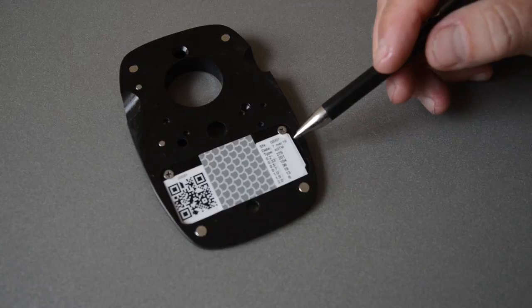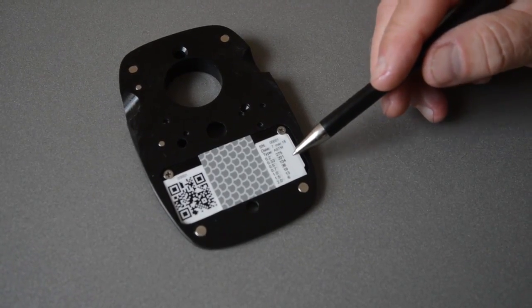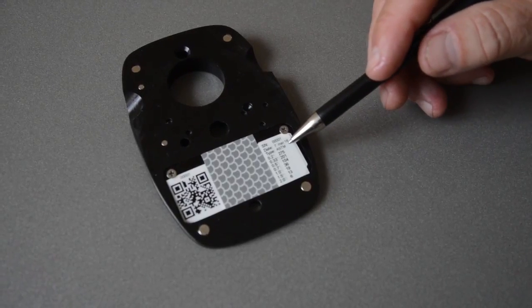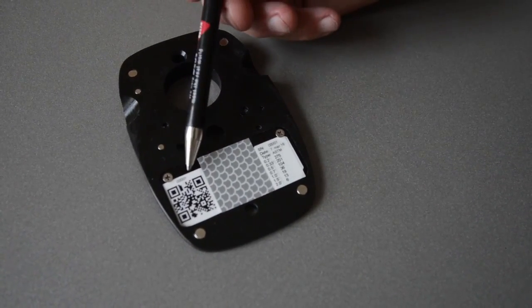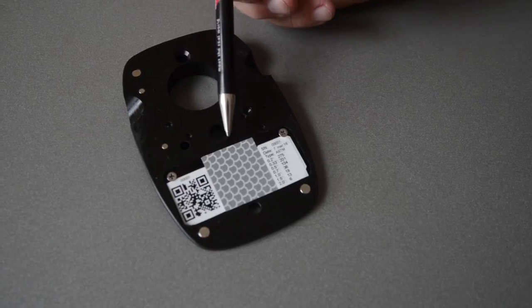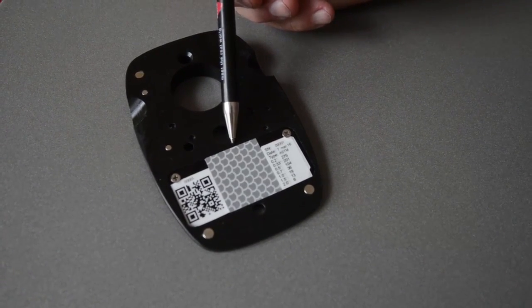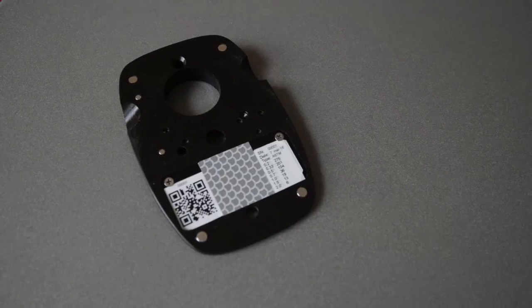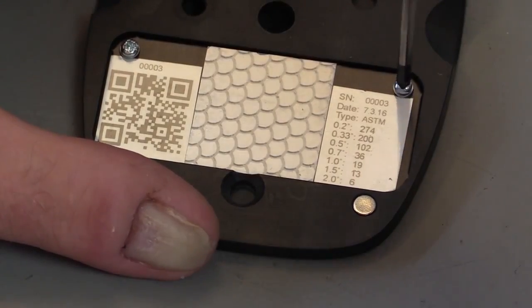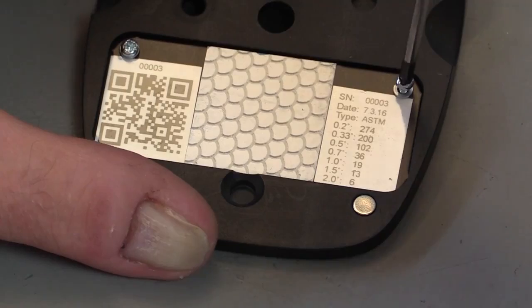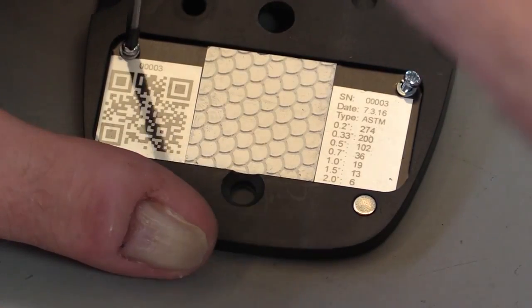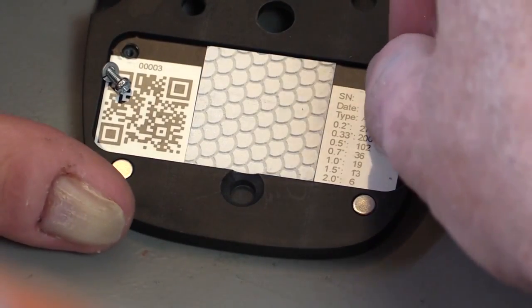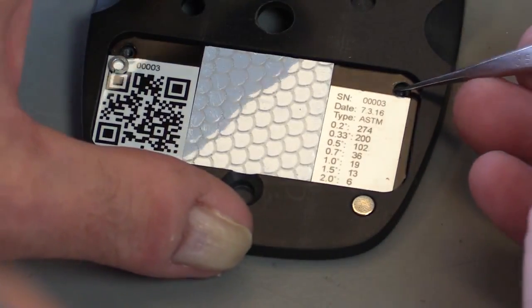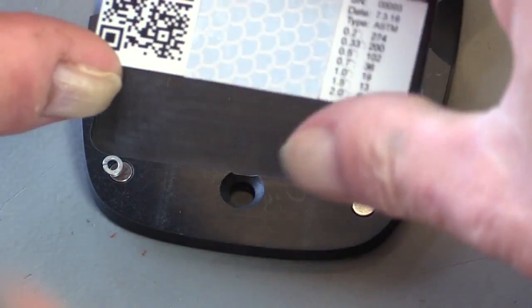To make sure that the calibration of the retroreflectometer is correct, it is important that the surface of the calibration target is clean and undamaged. Keep the calibration target protected and be careful not to touch the calibration target, the reflective sites. If the surface is stained, scratched or broken, the calibration target must be replaced. A replacement calibration reference can be purchased from Delta or from one of our service dealers and changed by the user by unscrewing 2 screws and replacing the damaged calibration reference.